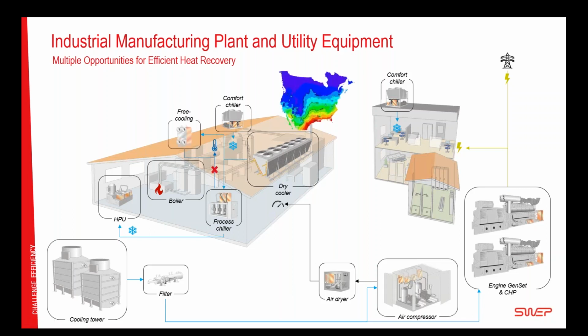What we'll start with actually is the free cooling. So what is possible to do is that if the ambient temperature is below the temperature of what you need to cool the process, and that could of course be an industrial process, could be an IT server hall, something that needs cooling even during the cold parts of the year. What free cooling means is that it's possible to have the dry cooler take directly the cold ambient temperature and cool the inside, and just closing off the process chiller, not operating the chiller at all.